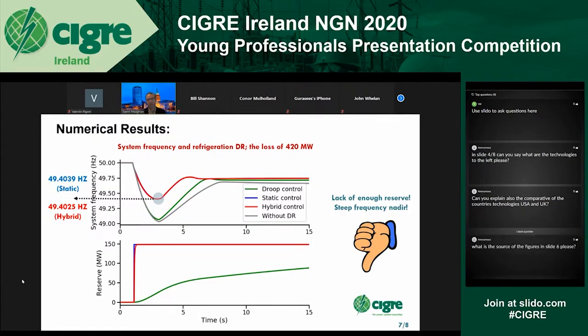It can be seen that the frequency nadir in all cases is not desirable, due to the fact that the size of available reserve in comparison to the event size is small. However, you can see that the static and hybrid methods are the most effective at improving the frequency nadir. I should say the worst response, the lowest frequency nadir, comes from the case in which demand response units do not contribute to fast frequency response service. Another point is that as a droop response depends on the frequency deviation, it results in a much slower increase in output as the frequency falls, and hence a steeper RoCoF curve and lower frequency nadir than the static and hybrid approaches, as can be seen.